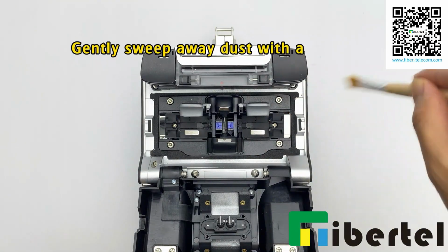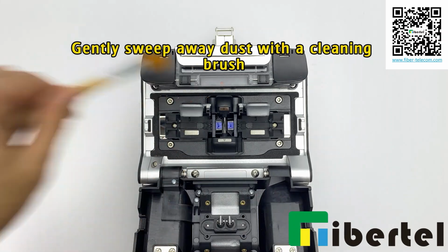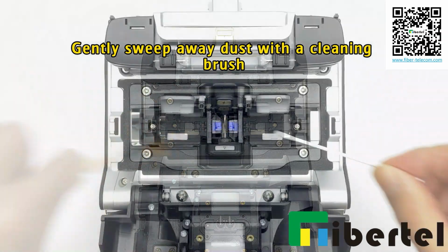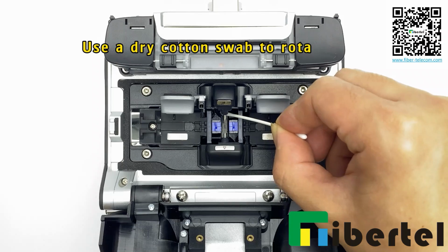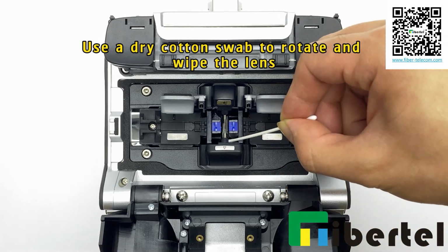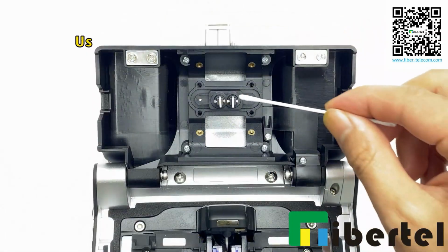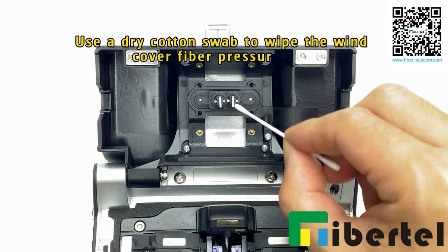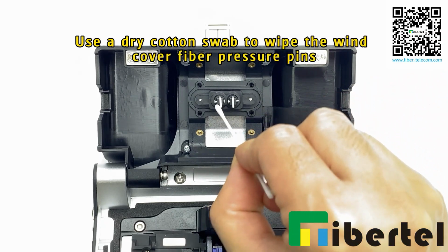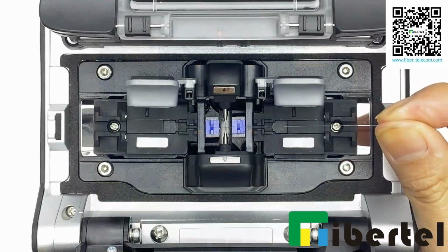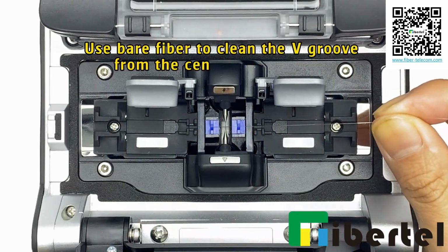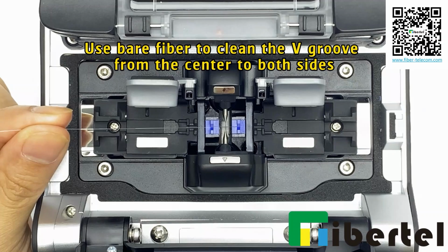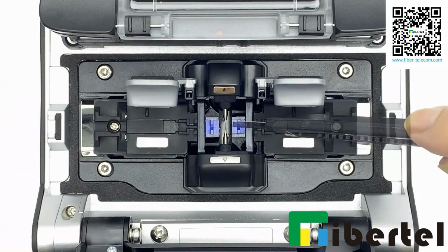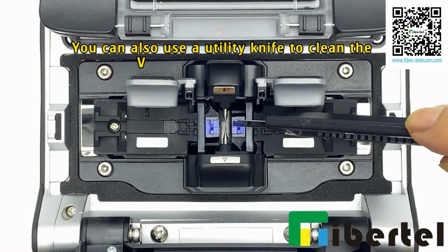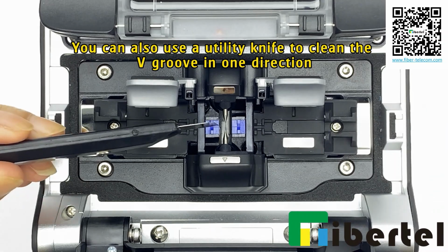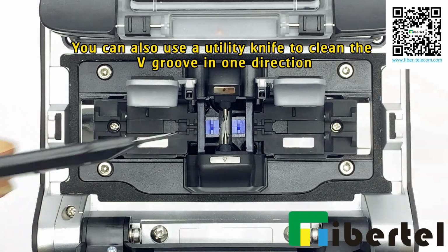Gently sweep away dust with a cleaning brush. Use a dry cotton swab to rotate and wipe the lens. Use a dry cotton swab to wipe the wind cover fiber pressure pins. Use bare fiber to clean the V-groove from the center to both sides. You can also use a utility knife to clean the V-groove in one direction.